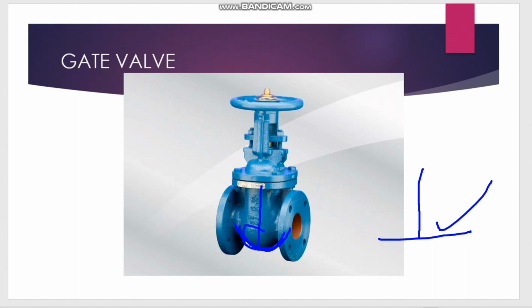There is a chance that sometimes dirt or dust particles may settle in the bottom of this arrangement - that's the metal seated type. Nowadays for gate valves we mostly recommend resilient seated, meaning the bottom will be straight, so there is no chance that dust or dirt particles will stay on the line, because the lines are very straight. So this is the first point.